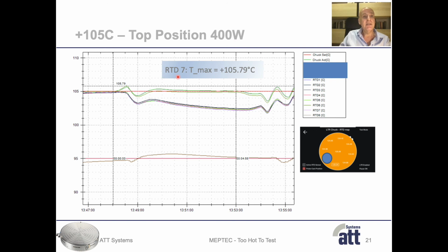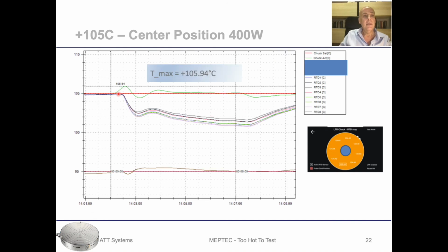Again, RTD7 became the control sensor. The maximum temperature reached 105.8 degrees C after applying the power. Then the system dissipated the entire energy and was able to control the temperature very stable around the set temperature of 105 degrees C. At the center position, exactly the same behavior. Maximum temperature was measured at 105.9 degrees C. The energy was fully dissipated, and then the temperature was very stable around the set value.